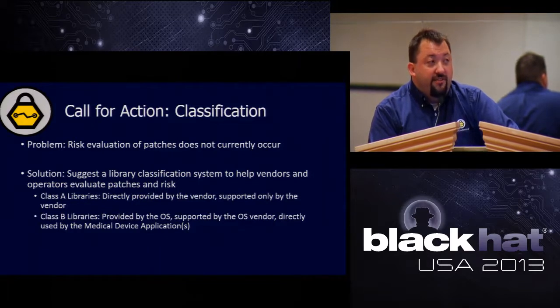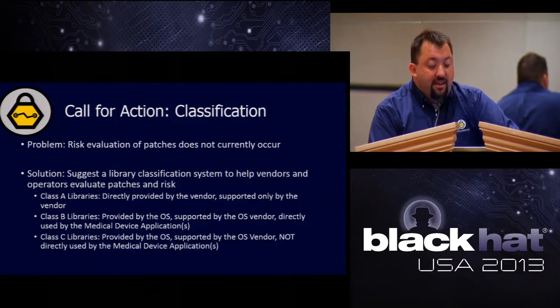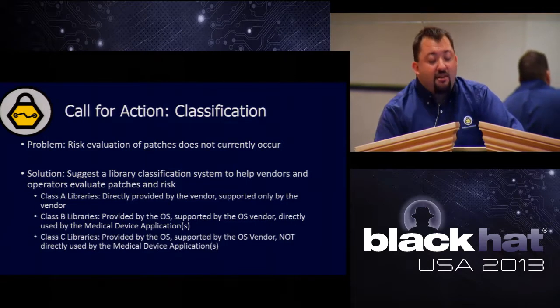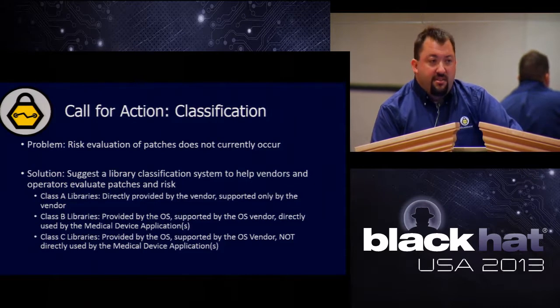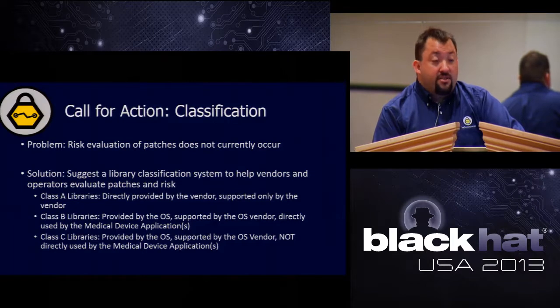So if you know these 15 DLLs are being used actively by your device, you would list them. Class C libraries are provided by the operating system, supported by the operating system, and are not directly used by the medical device. That way, when you look at the patch list for these devices, you can quickly determine, you know what, none of these libraries are used by this system, so I have the risk determination that it is low risk to patch this device.